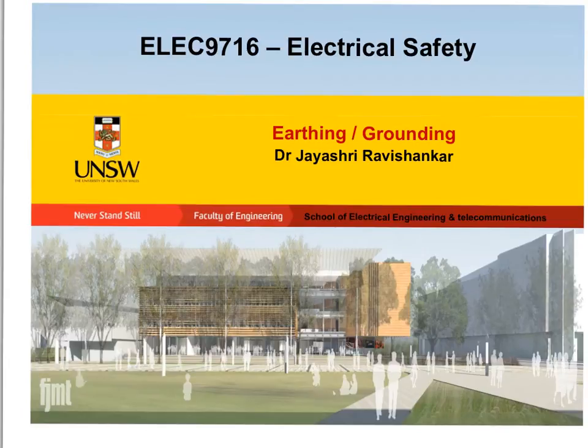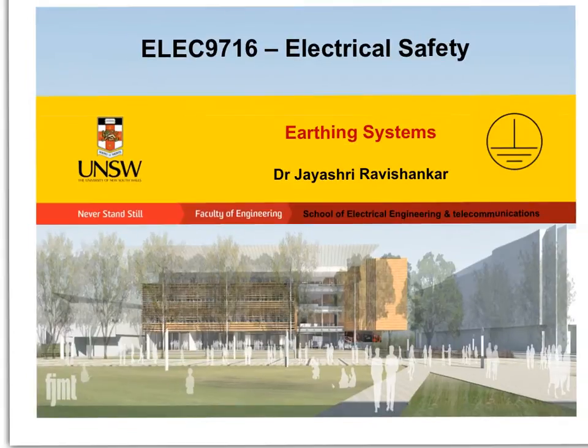The process of electrically connecting any metallic object to the earth is called earthing or grounding. Earthing systems are designed to manage the flow of fault currents to protect people and equipment. Fault currents, including lightning currents, are safely transferred into the earth through the earth connections. Earthing falls under class 1 insulation and it has this symbol.